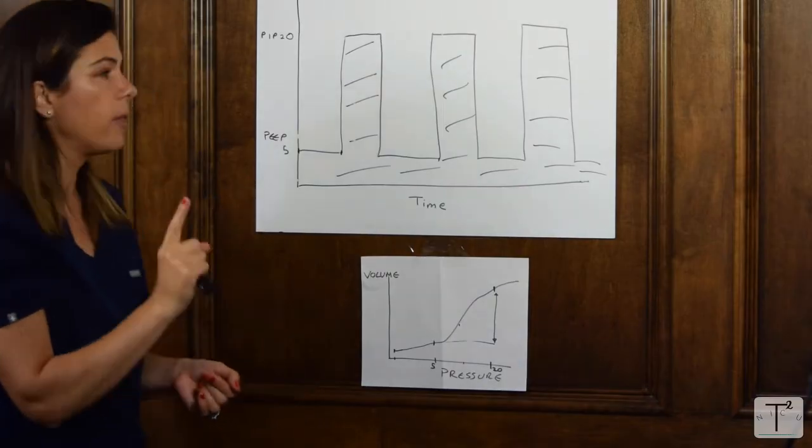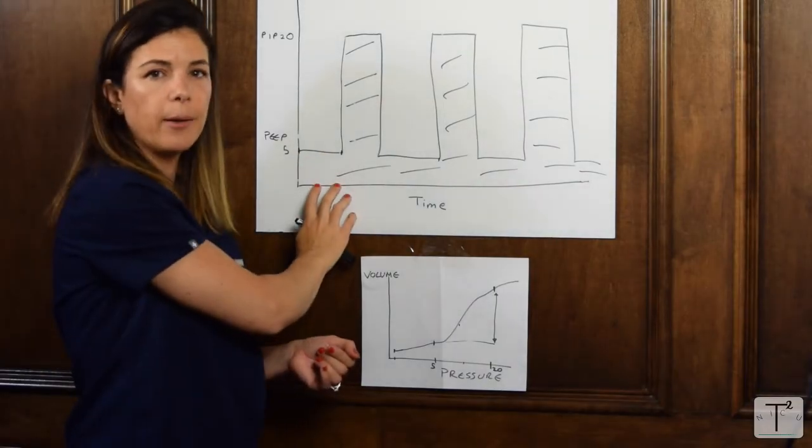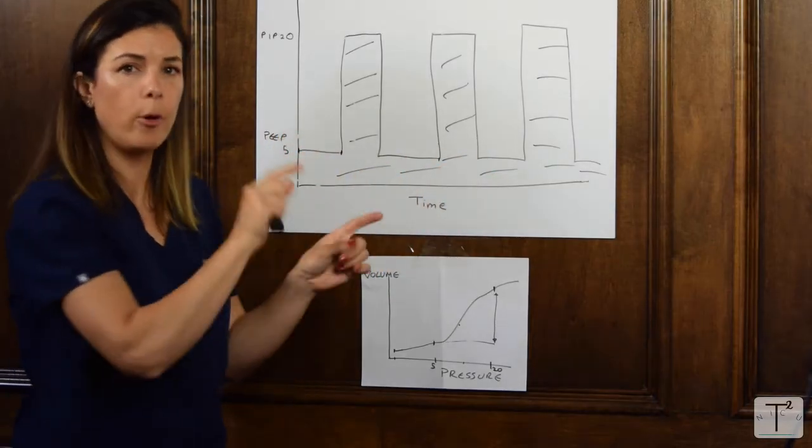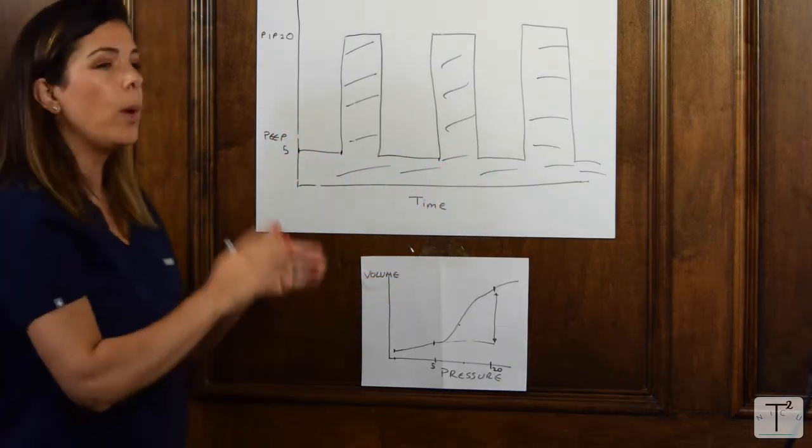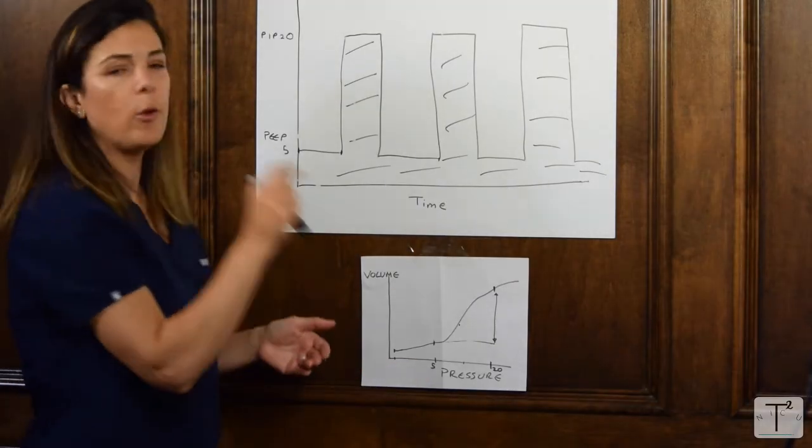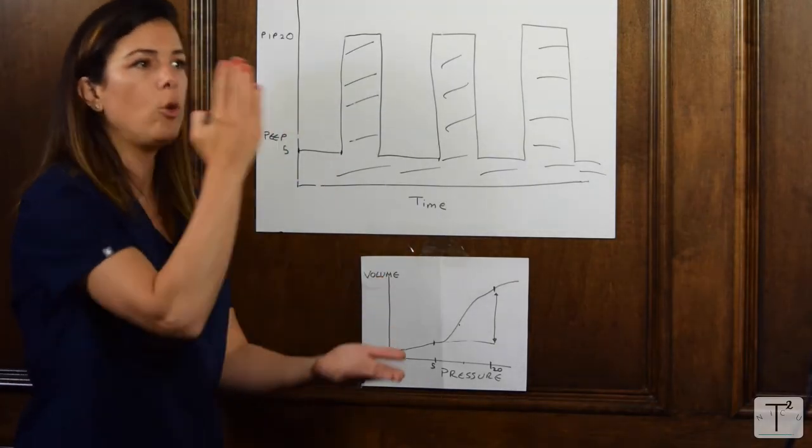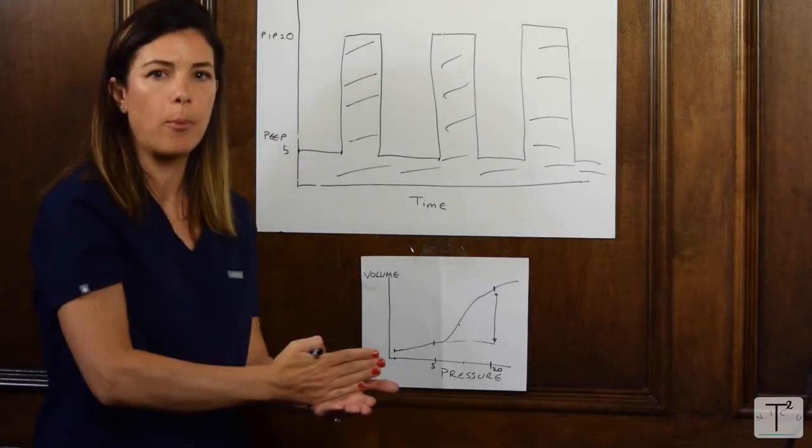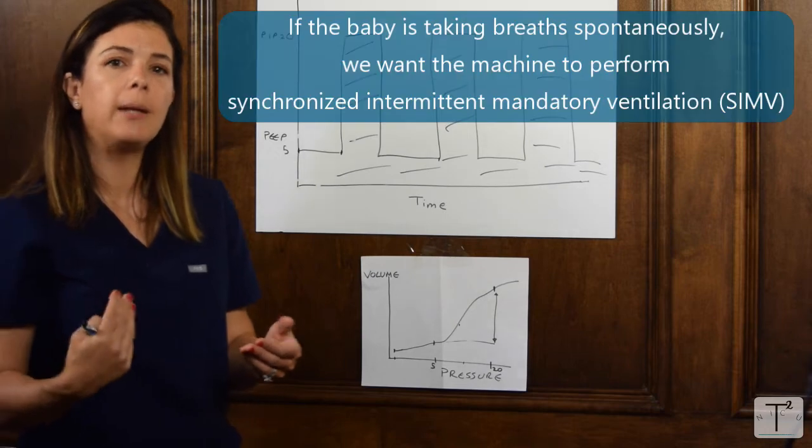There's just one more thing that I want to mention with the ventilator. For the purposes of this, this is again pressure mode because we're typing in pressures here. We are assuming that the baby is not taking any extra breaths by itself. Here, if you set the rate at 30, every two seconds exactly, the machine will take a breath. Whereas in reality, we want the machine to be synchronized with the patient.